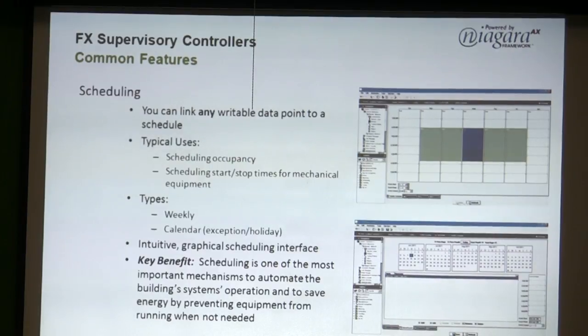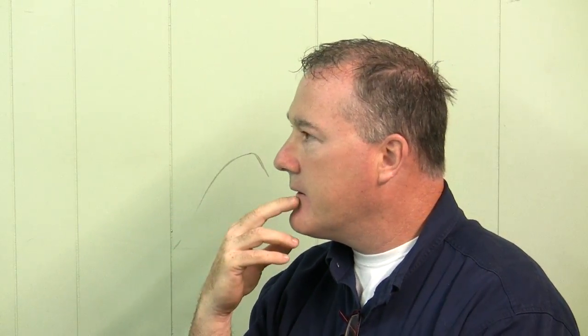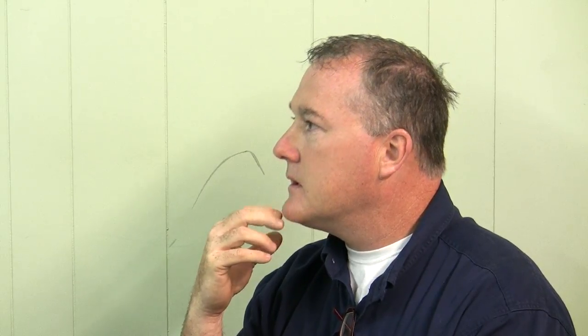These programs relate to controlling lights and other systems. If you have a Watt Master or your doors, parking lights, building lights, and architectural automation all on one system — yes, you can pull it all in. Those devices have a comm protocol. Your lighting wires back into a BACnet or LonWorks lighting panel, and one little comms connection daisy-chains back to a card slot on your Jace. There are also wireless 'bullet' devices you can install on parking lot lights that communicate back via ZigBee mesh.